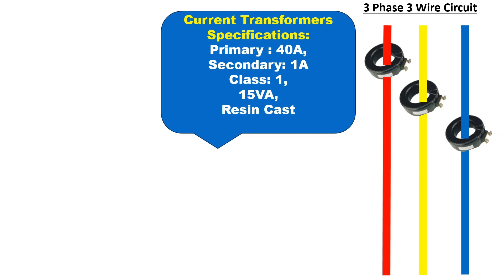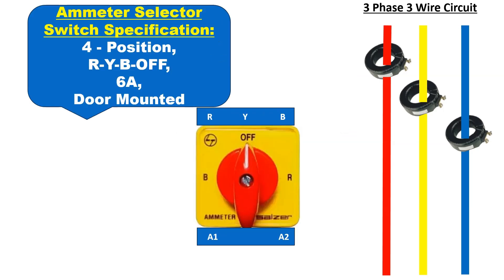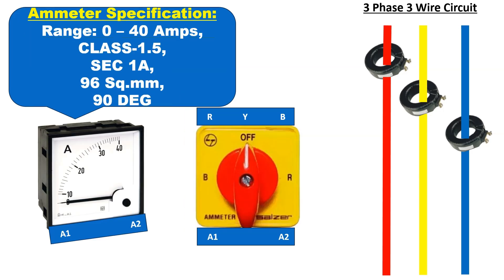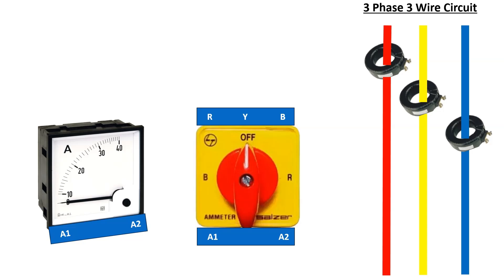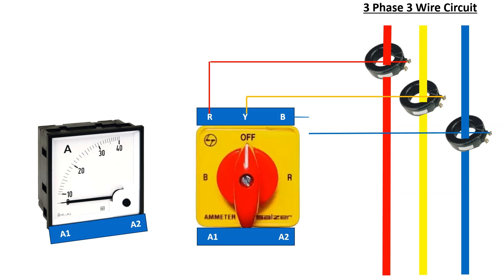Current transformers are installed in all three phases to step down the current. Now, we have added a four-position ammeter selector switch. Next, an ammeter is added in the circuit to measure the current. We will connect cables from the current transformer terminals to the R, Y, and B terminals of the ammeter selector switch like this.